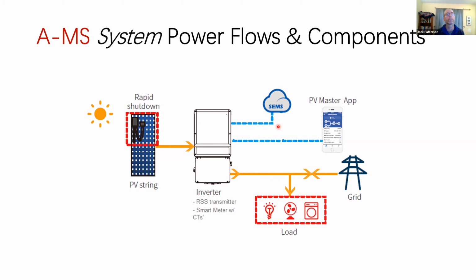That's our monitoring in the cloud system, which you can access via an app or on your computer, going to the website, that portal. And another way of connecting to the inverter is through our commissioning app and configuration app. So there are different ways to control and view what's going on with the inverter. What's not pictured here is that, as I mentioned before, there's an embedded smart meter with CTs. The CT lines would run out somewhere close to the grid connection, to be able to observe how much energy is flowing out to the grid, and what isn't flowing out that you produced must have been consumed. So that kind of consumption and export information is available on the SEMS platform.